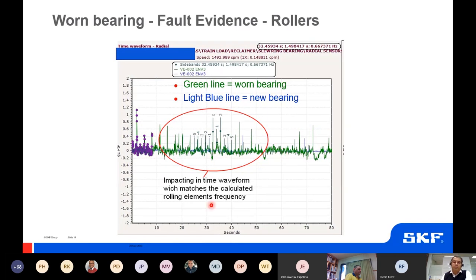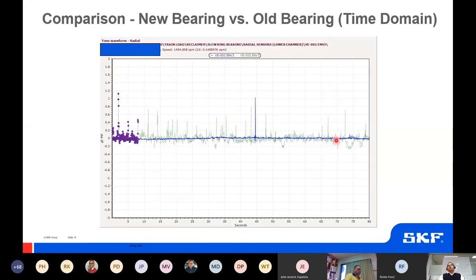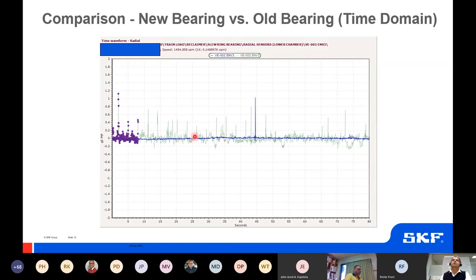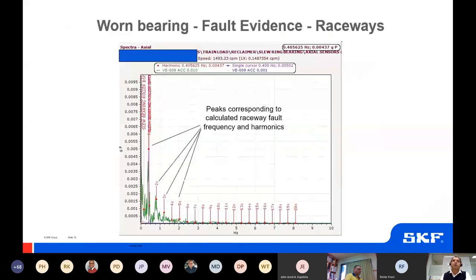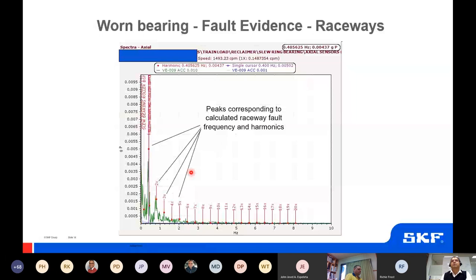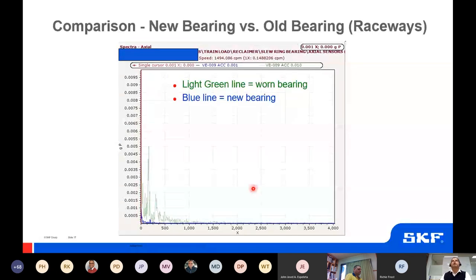Comparing time waveforms: the blue line is a new bearing and the green line shows damage, with clearly visible repetitive impacting in the green trace — nothing similar in the new bearing. Another spectrum shows raceway frequencies as well, with the healthy bearing on top in blue and the damaged bearing in green behind it.